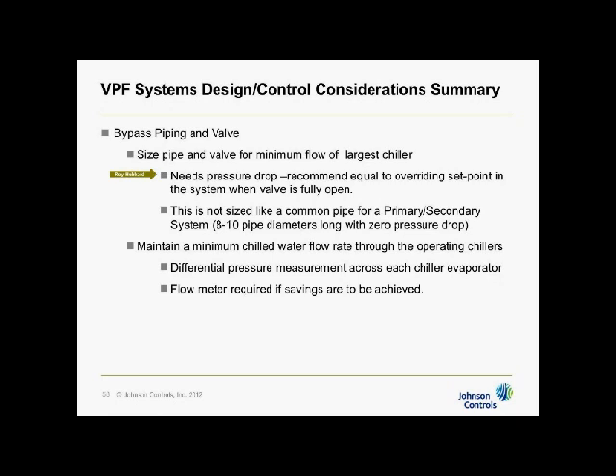But the point is, unlike primary-secondary, where I want zero pressure drop, I do want pressure drop here so that I can move water in either direction easily. Again, with primary-secondary, we do 8 to 10 pipe diameters with zero pressure drop, but here I'm trying to get the pressure drop in this. So it's much smaller. In fact, quite often, the bypass valve is sized one size smaller than even the pipe to increase the pressure because it's not easy. So this is a small pipe versus primary-secondary. Primary-secondary is a large pipe.